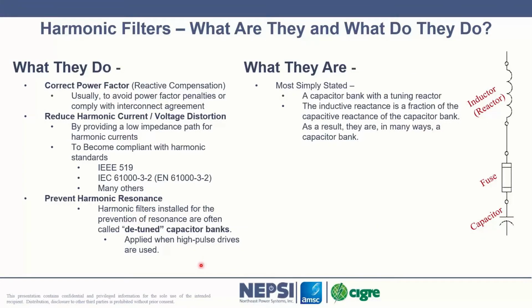Harmonic filters, what are they and what do they do? And this is a key point that I often like to cover first. Harmonic filters in general are installed for three primary reasons. The first one is to correct power factor. And this is something that some people may not understand: most oftentimes a harmonic filter is being installed to correct power factor. That's the dominant reason why the harmonic filter is being installed.